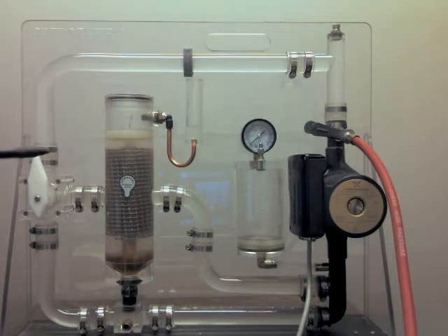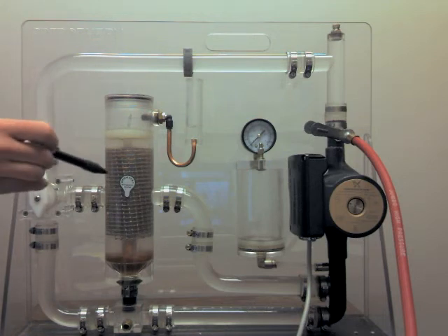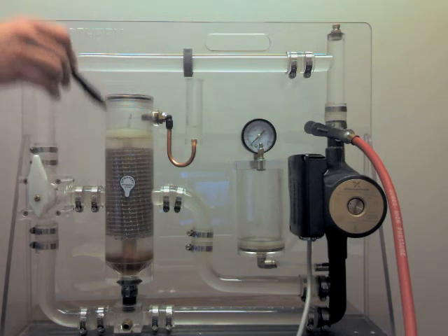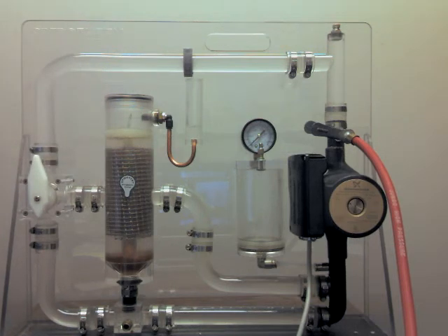The other equation, with just slowing the water down, is filling it up full of this media, which takes out the turbulence in there, and that's what makes things calm and these little bubbles are able to rise. The other part of its engineering is to attract air bubbles, which is where the coalescing term comes from. They adhere to this mesh and other bubbles collide into those, and once they become big enough, their buoyancy just carries them up to the top.